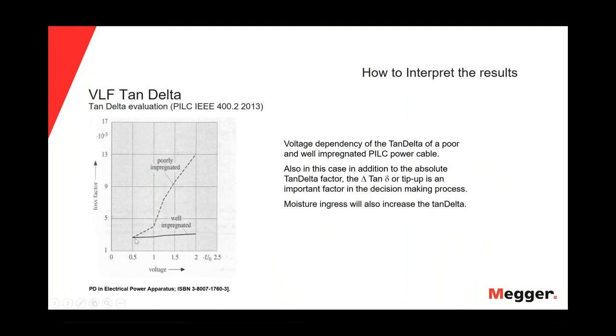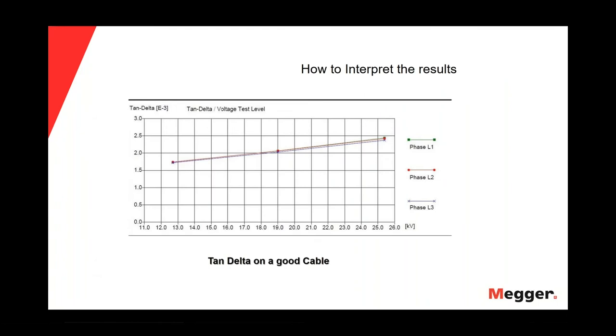And we have this situation also in paper impregnated lead cables. If you see this graphic, we can see that for well impregnated cables we have almost a flat line, but for poorly impregnated cables we have an increase of the tan delta as we increase the voltage, okay? How to interpret the results?